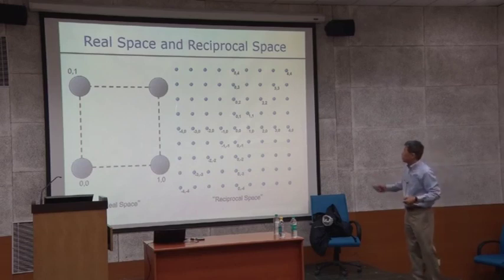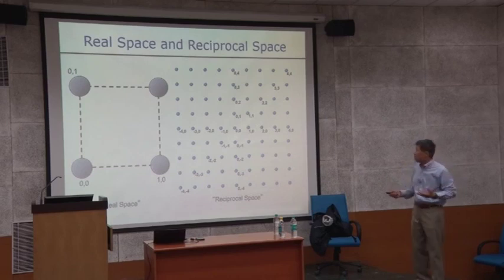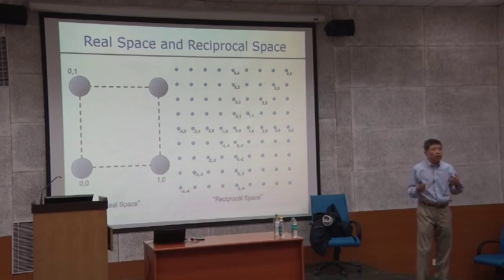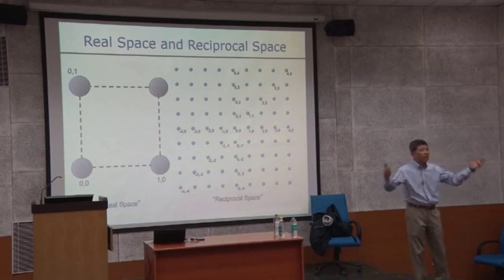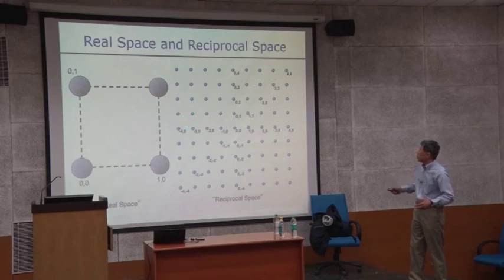So for most reciprocal lattices you actually see in papers, when you describe your samples, you just cut a certain slice of the reciprocal lattice. And when you cut the slice, you don't want to show all of them because your diffractometer cannot access all of those. Because of your real space angles, you cannot reach a certain theta value, you cannot reach a certain chi angle, so you can maybe access only this much. You cannot access this, maybe only within a circle, within that area. Get it? So sometimes your accessible points may be this much, in this shape.